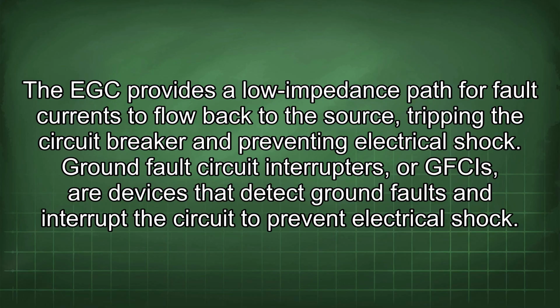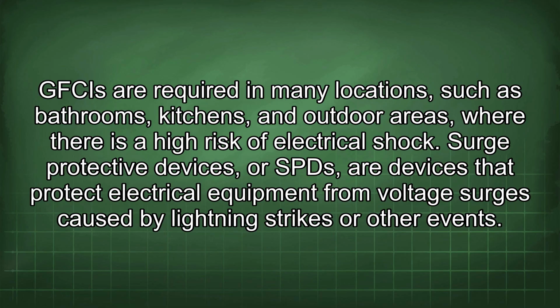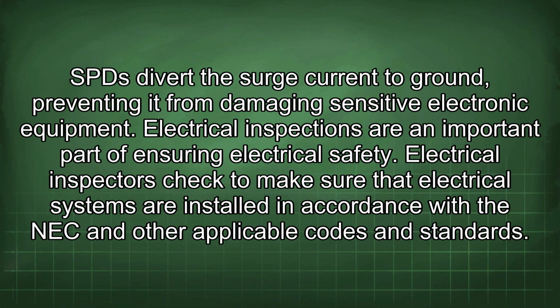Ground fault circuit interrupters, or GFCIs, are devices that detect ground faults and interrupt the circuit to prevent electrical shock. GFCIs are required in many locations, such as bathrooms, kitchens, and outdoor areas, where there is a high risk of electrical shock. Surge protective devices, or SPDs, are devices that protect electrical equipment from voltage surges caused by lightning strikes or other events. SPDs divert the surge current to ground, preventing it from damaging sensitive electronic equipment.